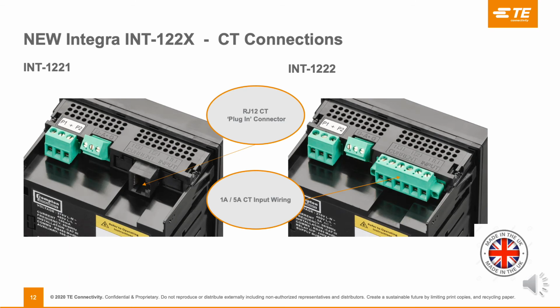Okay, getting down to the actual connectivity of the meter. Obviously the two models, the Integra 1221 is to the left. As you can see, this is an RJ12 CT plug-in connector. Simple to use. We have a range of CTs that has a lead as standard supplied. Plug the CT lead into the meter and that's as easy as it gets. So the one on the left is the 1221, which is an RJ12 CT plug-in connector, and the one on the right is the Integra 1222, which is the 1 amp and 5 amp CT input wiring. They are plug-in connectors to make it easier to connect the wiring, then plug the actual plug into the meter.